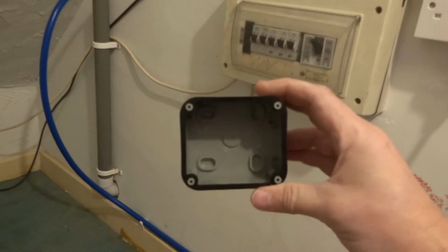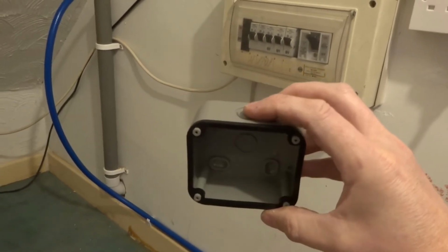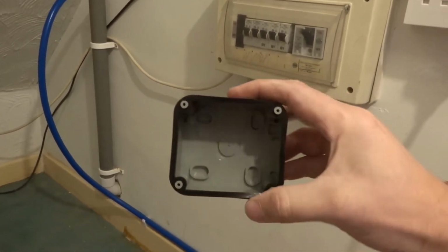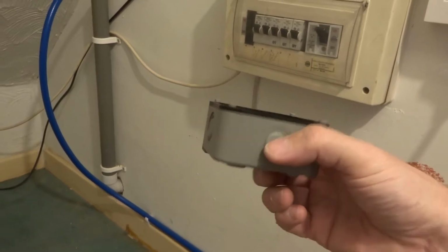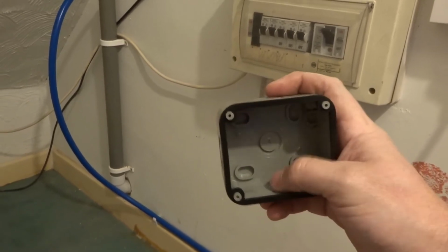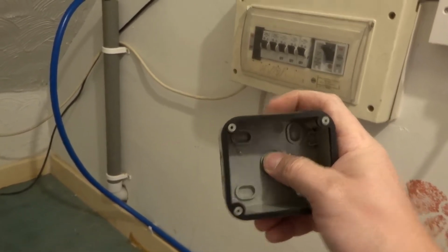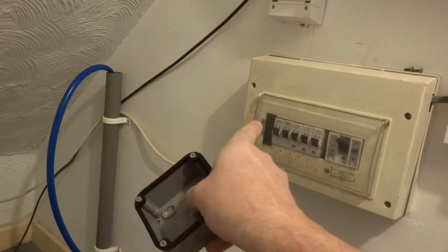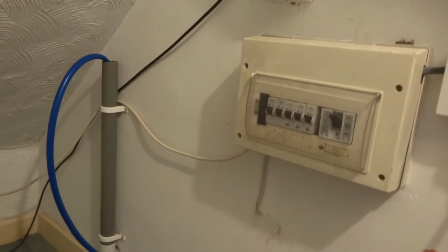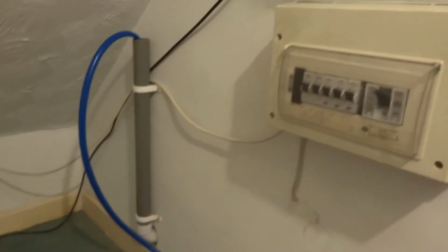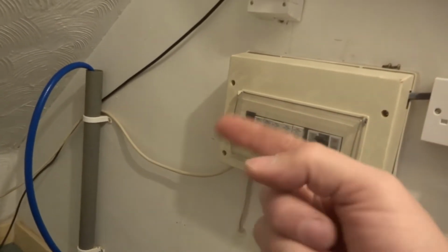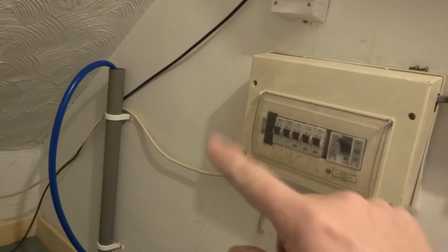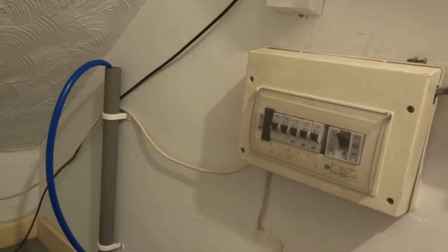Then the armoured cable is going to terminate outside the house in this box. If you want to see how I do the termination of the armoured cable, watch one of my other videos. Basically, the armour will terminate here, then there'll be a hole in the back. I'll have a piece of conduit running through the wall to protect the cable, and the inner sleeve of the armour cable with the three wires will come into the white bit, into this. Then I'll strip back the inner sleeve and run the three wires to the breaker on that side as well.